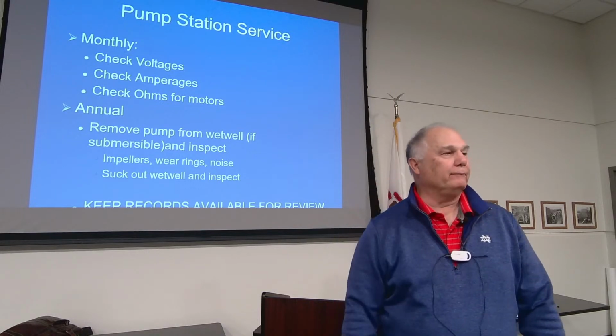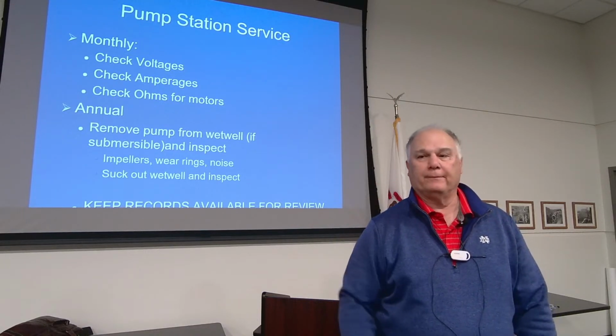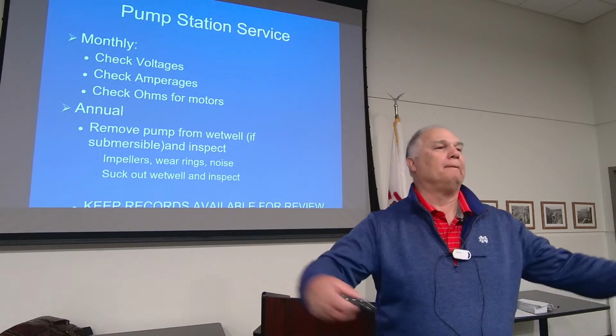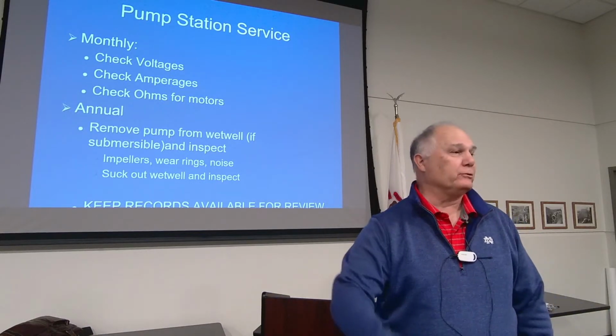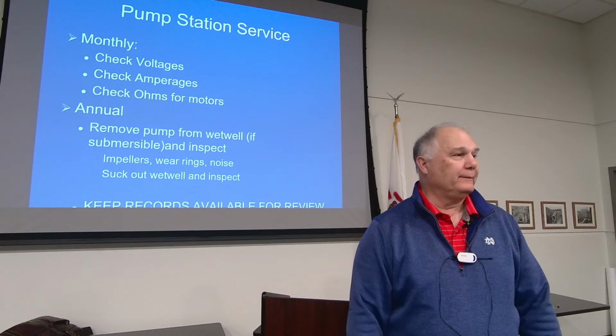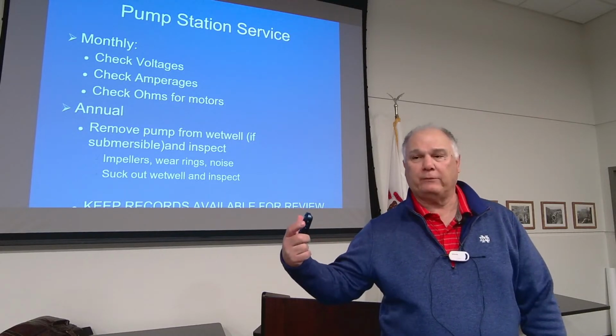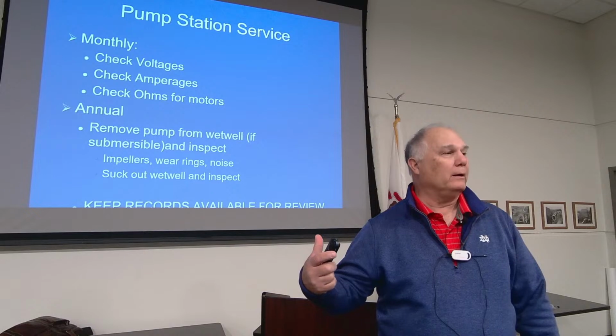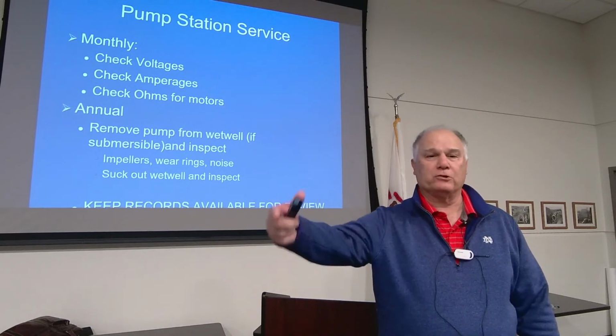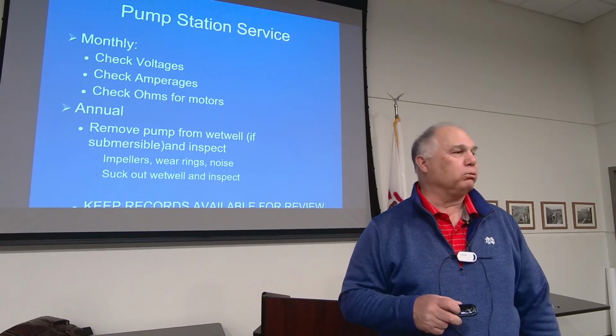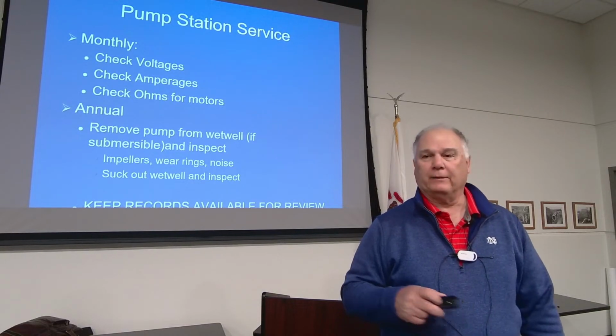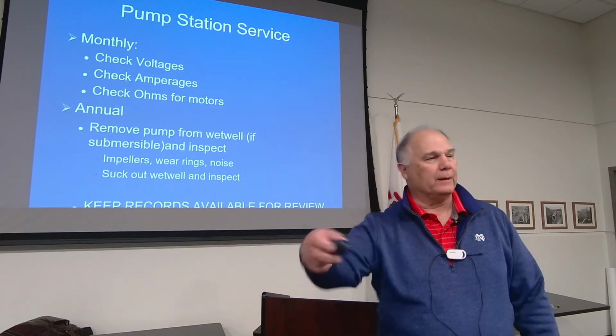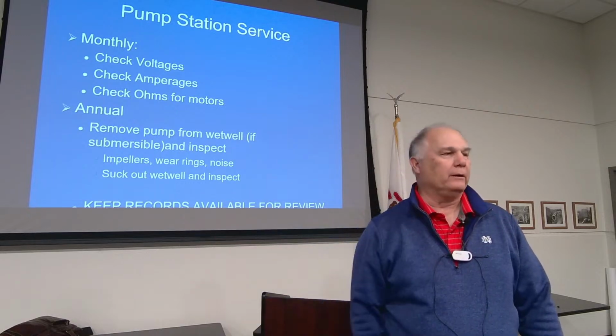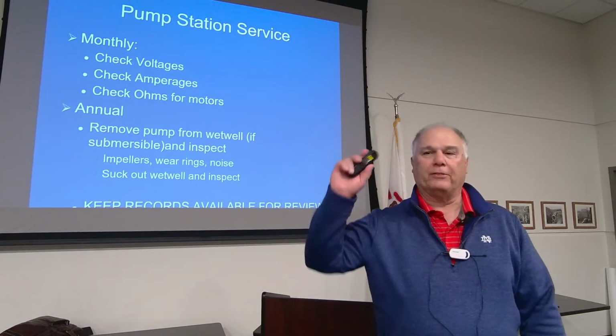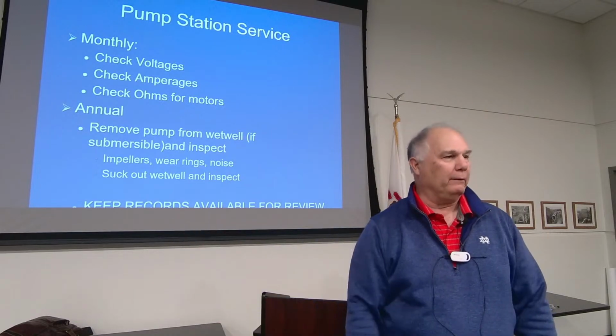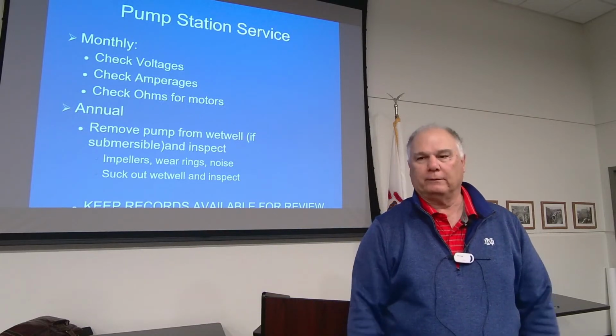Southern Missouri, high head applications. They called me up one day and said, hey, your station isn't running. The pump's running, but you're not getting any flow out of it. Remember I was talking about wear rings in the past? Well, they were out there digging up the force main, thinking it was plugged somewhere. They go out 500 feet, dig up the force main, and water's flowing out like it has no end. They go 1,000 feet, same thing. Like, what the hell's going on?